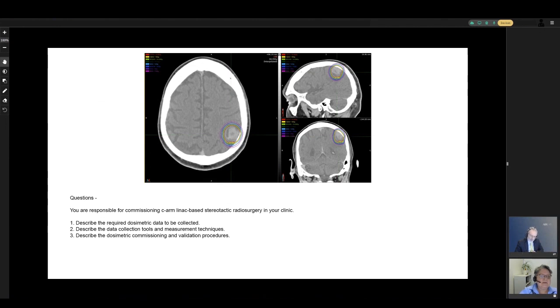Okay, so we're talking about small fields. Can you tell me a little bit about what you consider a small field to be? Yeah, so in general, as a rule of thumb, anything that's 3 by 3 centimeters or less is considered a small field. But it really is a field where you're losing lateral scatter equilibrium, or where the source is obscured, or the size of your detector is approaching the size of your field. Any of these conditions make it small field dosimetry.